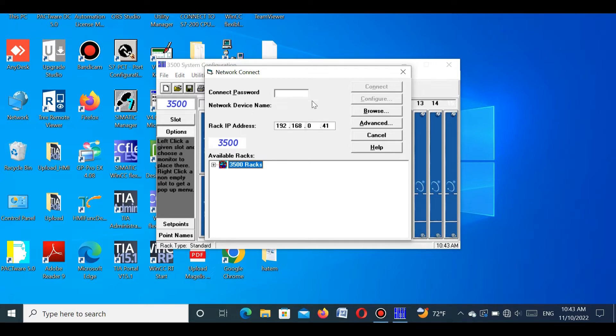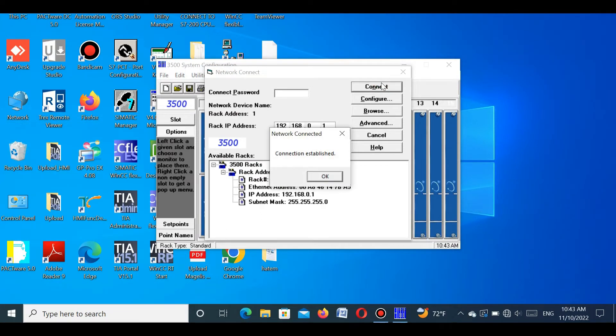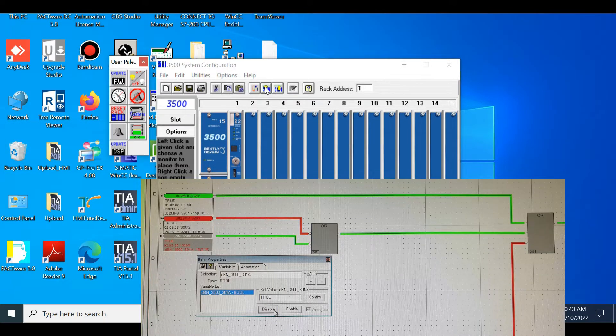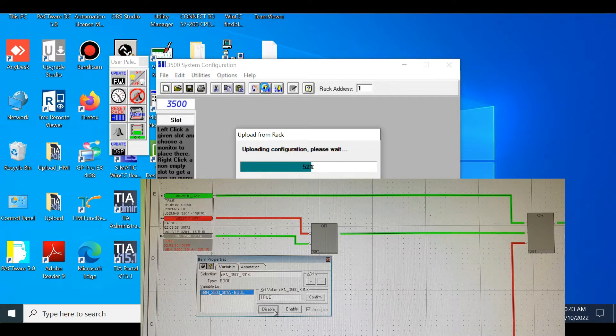Before doing that, I have to tell you that if you want to change any card or module of the Bently Nevada 3500 system, first you must bypass the communication system. If you do not bypass the communication system, the machine can be tripped when you change any card. For safety, you must first bypass the communication system.